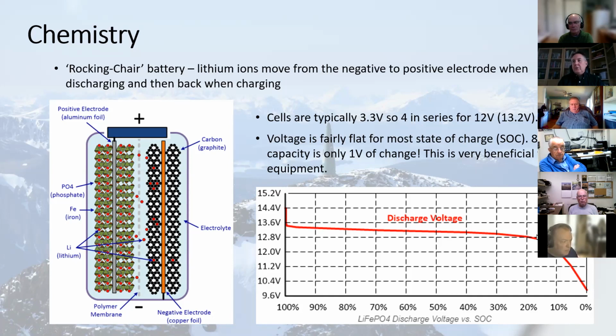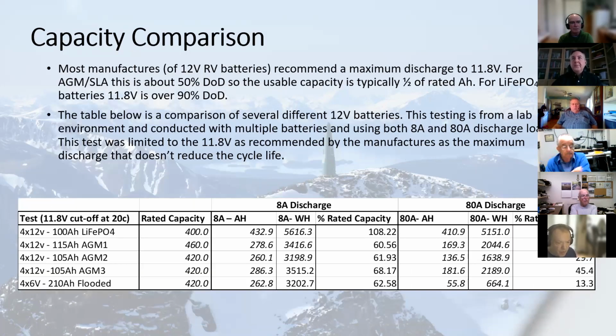And they don't start dropping until well over 80% of capacity. So your entire usable load range is all within 1 volt of the optimal voltage, so you see very little change. They're also not subject to the same kind of sagging that you see from a sealed lead acid under load. Sealed lead acid under load will read a lower voltage than one not under load, whereas these are very constant, and make for a real stable platform for equipment.